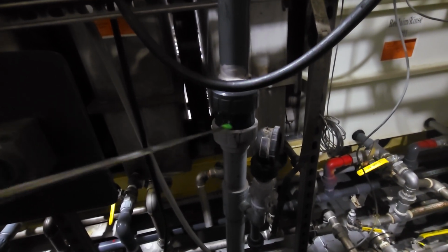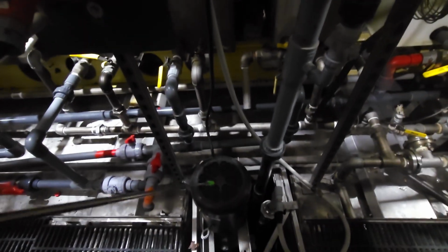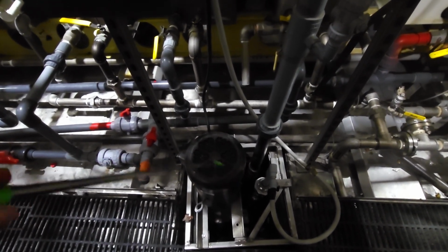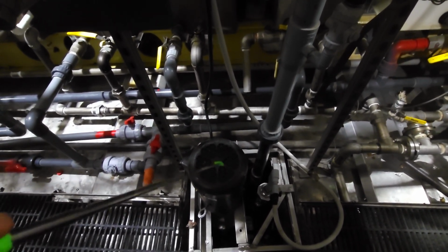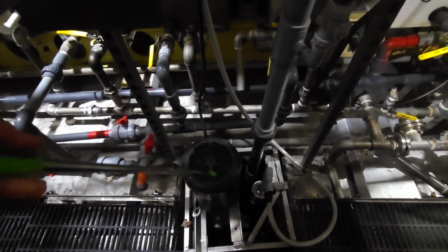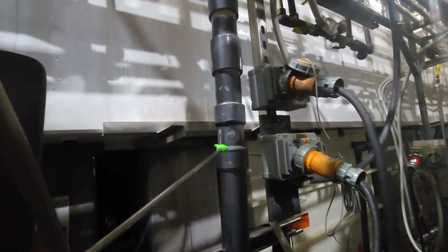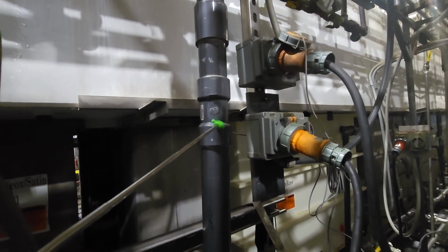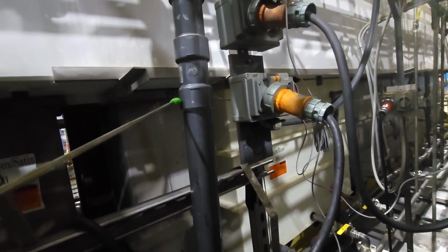Check valve. If your check valve is stuck, your pump's going to run, but you're barely going to be flowing out, or it could be flowing out great. However, to know it's bad, watch for your fans. If your fans backspin after shutting off, they're going to spin for a little bit after shutting off, but if they backspin, you've got to change your ball check. If you're not getting no flow, but your pump's empty, it's your flow sensor.